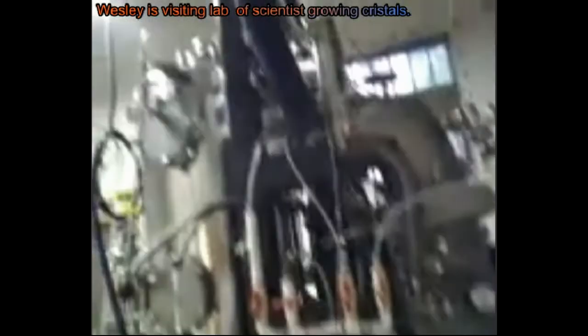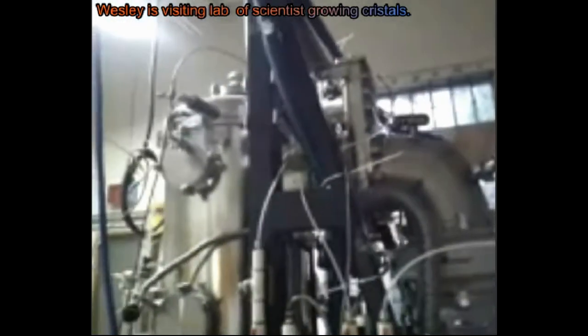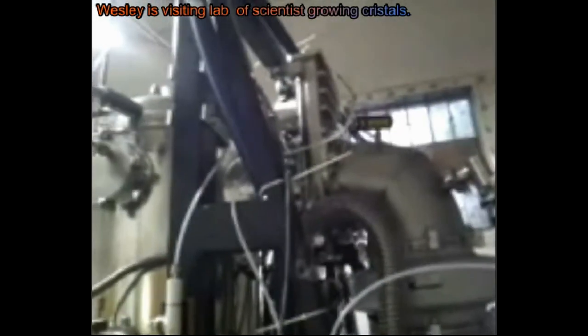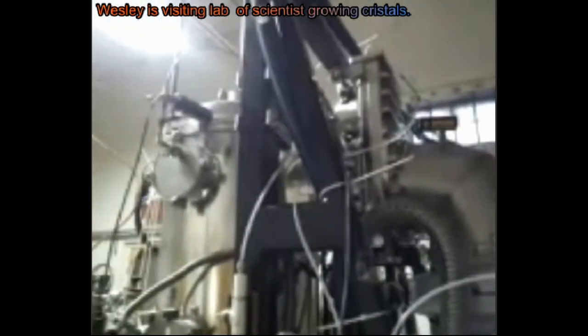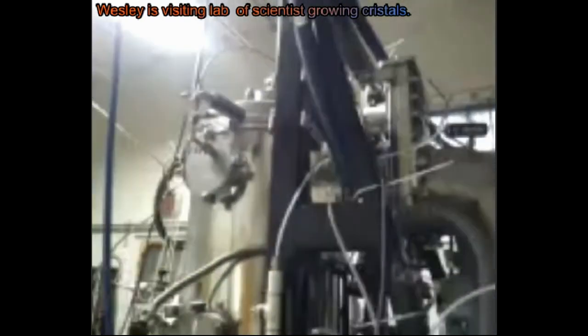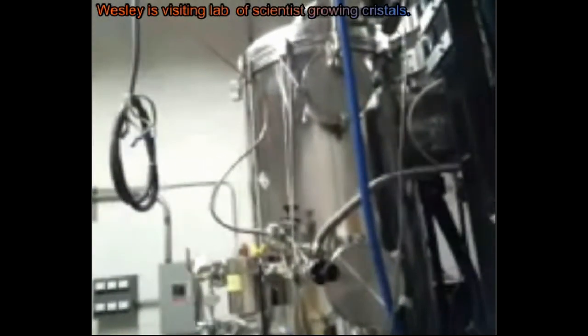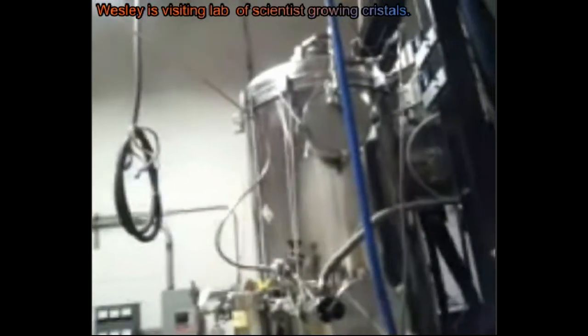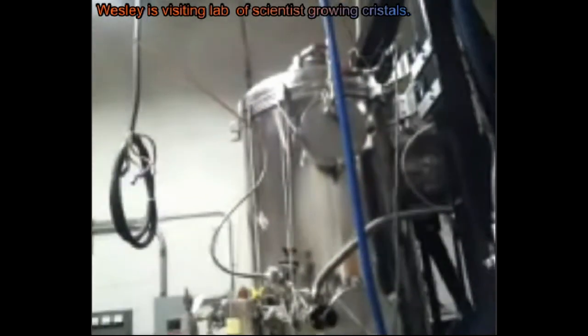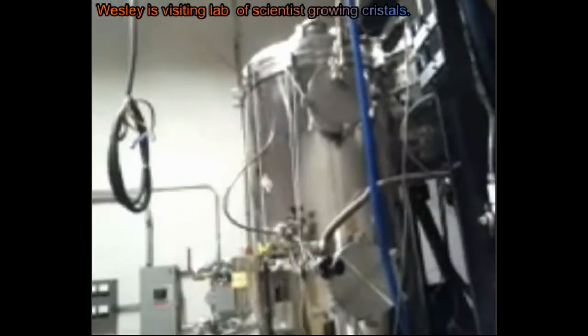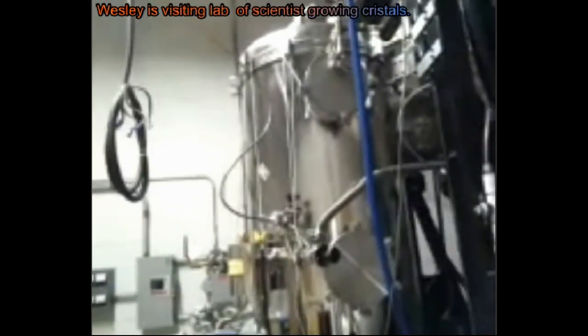There's also another interesting vacuum gauge there, the capacitive manometer. Could you say a few words about it? The capacitive manometer is just a diaphragm that deflects under pressure and then changes the capacitance between two plates. Okay. Now we have two openings in here. They are nicely closed. Usually people have a nice round piece of glass there. No, this gets very hot. So what temperature is there? This will go to about 3,000 degrees Celsius, which is more than the melting point of iron. Yeah, 1800 would be the iron melting temperature.